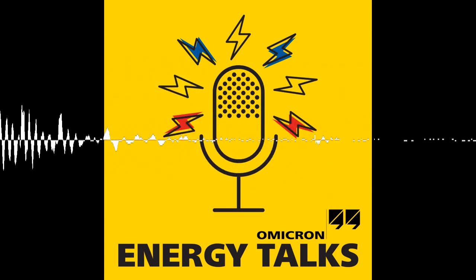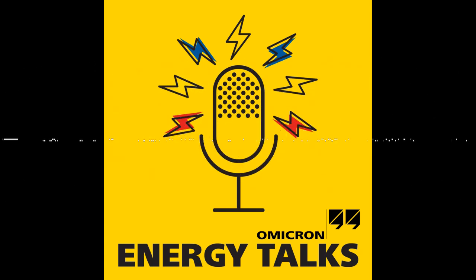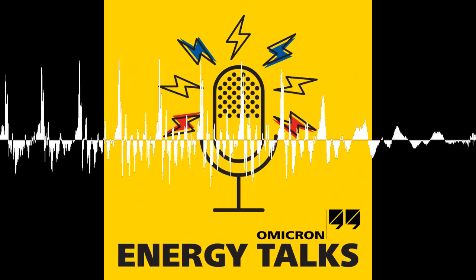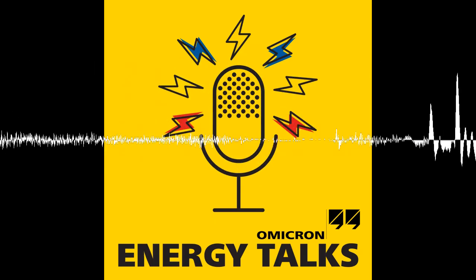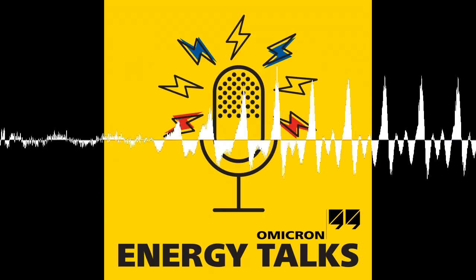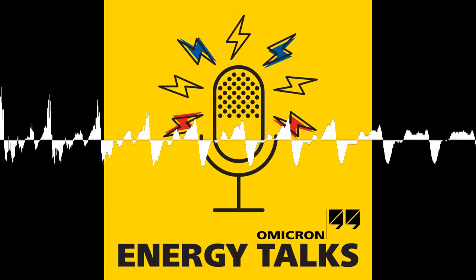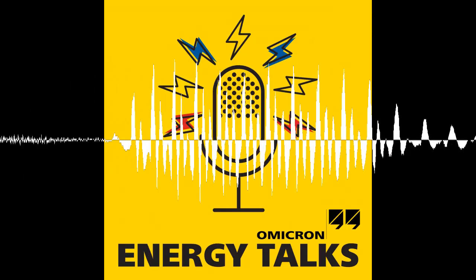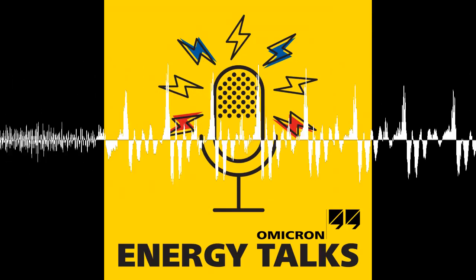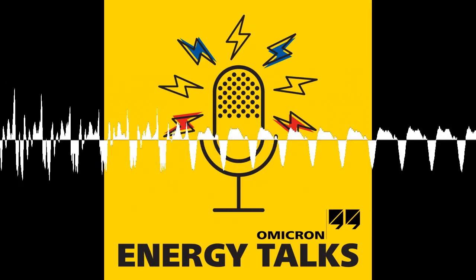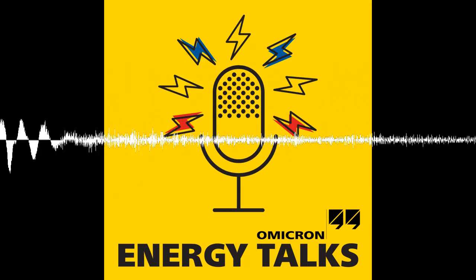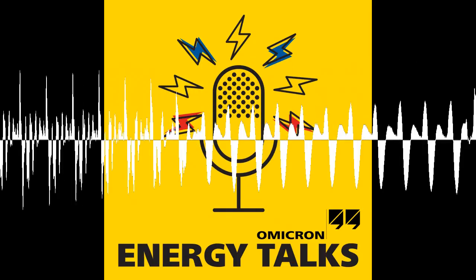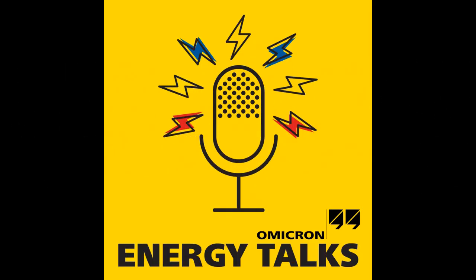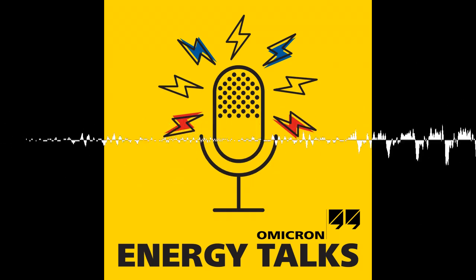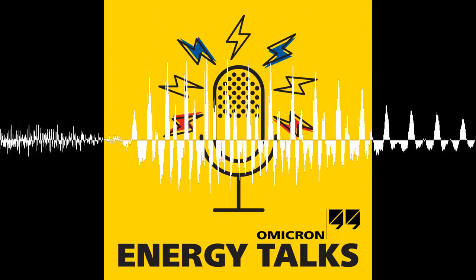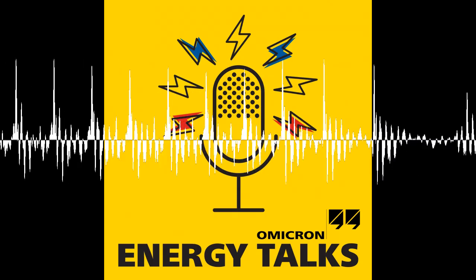Daniel, we're talking about partial discharge testing and monitoring. There are various ways to look at partial discharge activity in electrical assets: offline PD measurements, online PD measurements, and PD monitoring. Is there a particular method that is most used in the industry? Well, historically, the offline measurement is the way to go. But nowadays, we are seeing more and more the tendency to use online measurements or to go for monitoring of electrical assets.